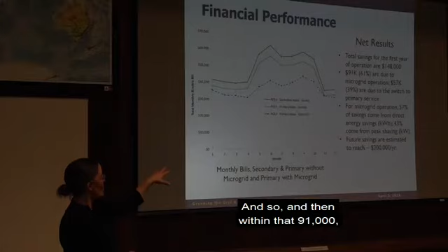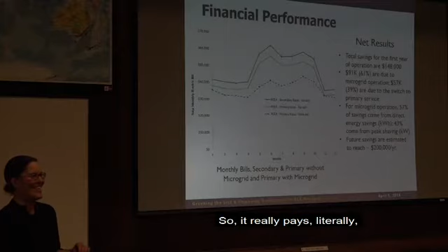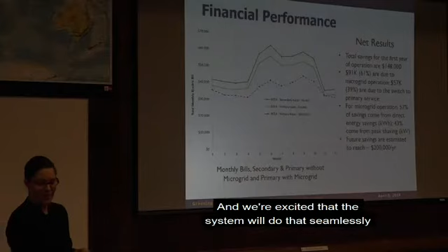And then within that $91,000, 57% comes from direct energy savings and 43% comes from the peak shaving that Peter was talking about earlier. So it really pays, literally, to pay attention to peak shaving, and we're excited the system will do that seamlessly for us, without us having to watch a 15-minute price point on power or anything like that.